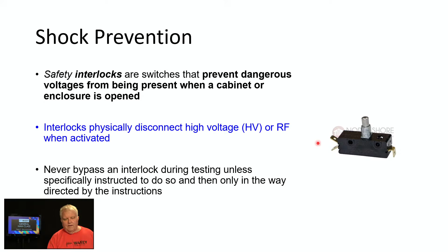And interlocks are switches that look like this right here. They sit flush in a case. I'll show you another picture here in a second. The purpose of the interlock is, if you pull the case, so here's an Alpha amplifier, and we've pulled the case off of the amplifier, and down here, it's kind of hard to see, but there's an AC safety switch. When the case comes off, the power supply is disabled in order to remove voltage from the cabinet.